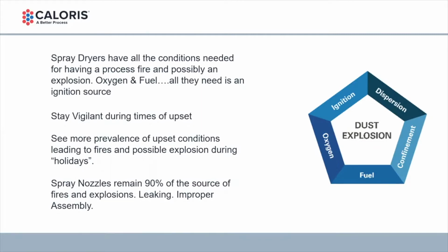As we go through this 30-minute presentation today, keep in mind when you're working with a spray dryer that, historically, through fires I've investigated, events I've read about, and data that's been collected on fires and explosions, the spray nozzles in a nozzle atomization dryer have been the source of 90% of fires and explosions. They may be leaking, or there may be improper assembly, but the spray nozzles remain the primary problem.